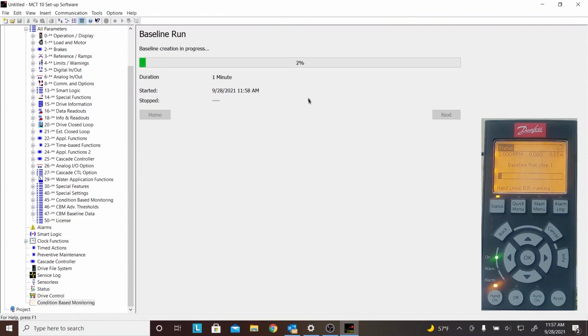Now we've initiated a baseline start. Now you can see it starting here. It's gathering data from 100 to 1700 RPM. It's pulling in the vibration, the motor winding data, and also the load data. And you can see on the keypad also that it's running the baseline run. Now you can see it's running, it's in hand mode. We're gathering all that data. We're time stamping it, date stamping it when we start and stop. And we know the duration, how long it's going to take to gather this data.